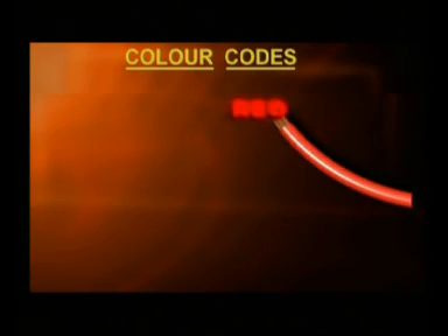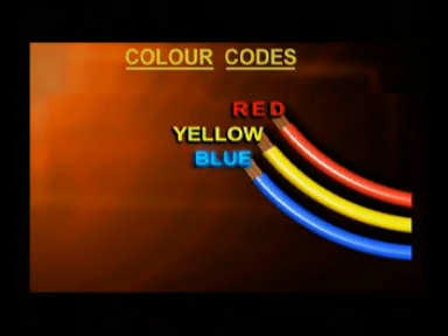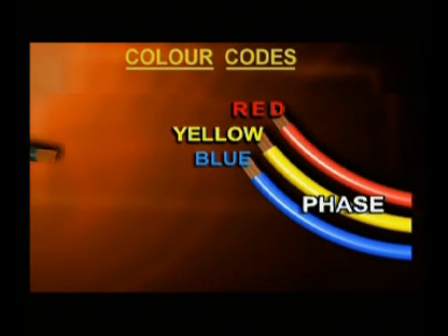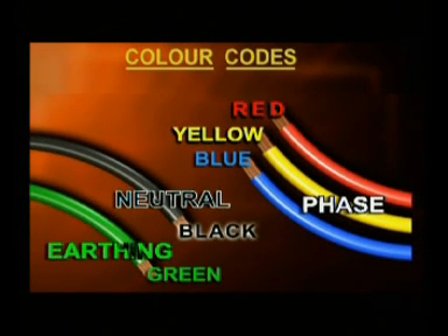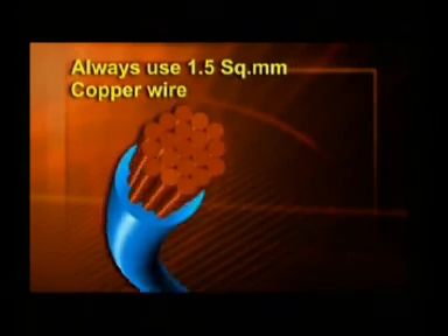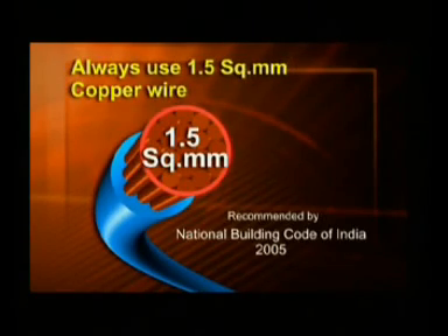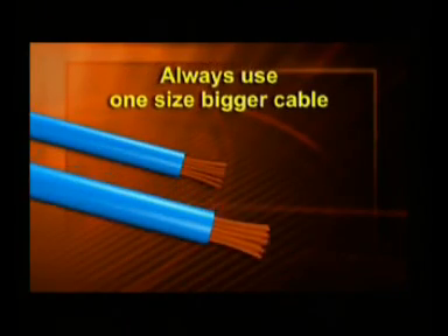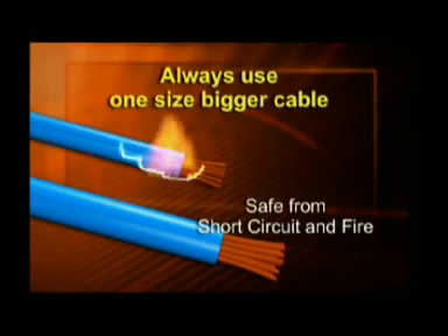Let's take a look at the phase color codes. As per the RYB code, R means the red cable, Y means the yellow cable and B means the blue cable. Always use black cable for the neutral and green for the earthing. You must follow this color code as per the Indian standards. The National Building Code of India 2005 suggested that the minimum size of the copper wire to be used should be 1.5 square mm. This will enhance your safety. Try to use cables which are one size larger. This will help to minimize the chances of fire in the event of a short circuit and overloading.